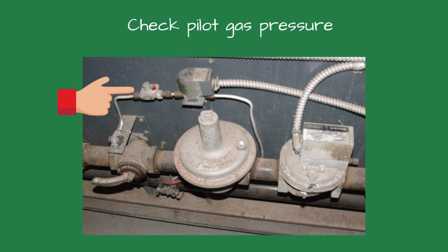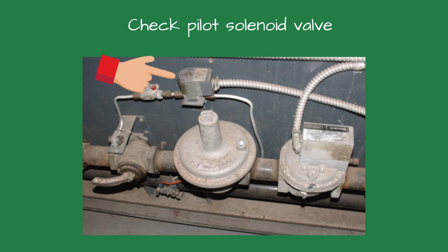Number 6 is adjust pilot gas pressure. A surprising fix is that lowering the gas pressure often stabilizes the flame signal. Higher gas pressure results in a turbulent, unstable pilot and signal drops. Use a manometer. Target is about 3 to 5 inches water column for natural gas, but verify with the manufacturer. Adjust the pilot regulator screw slowly while monitoring the flame signal and leave it where you get the best flame signal.